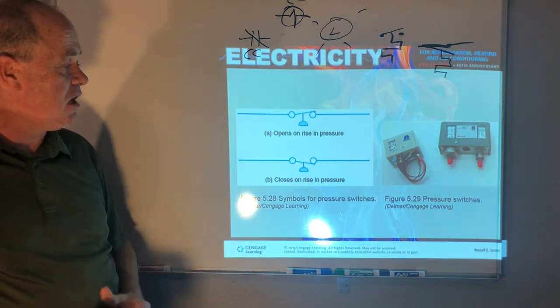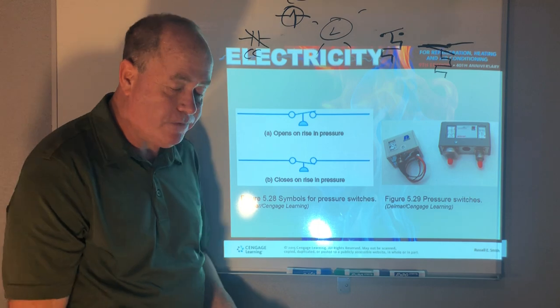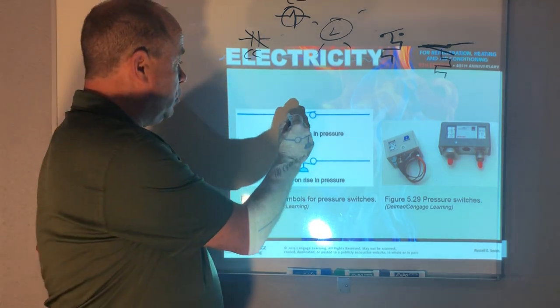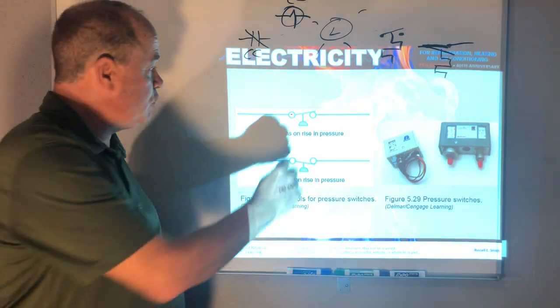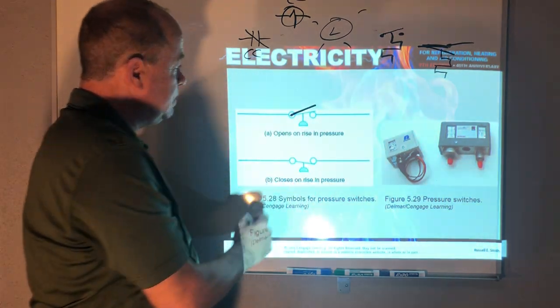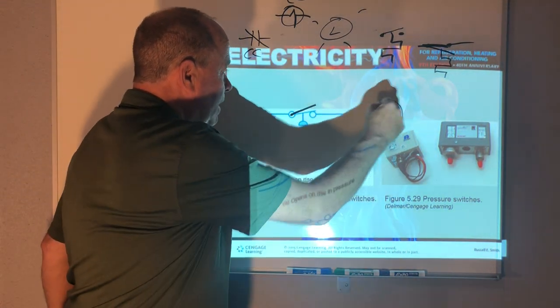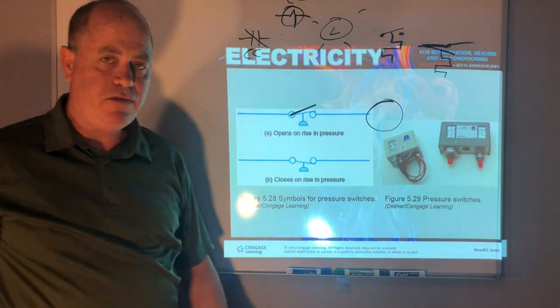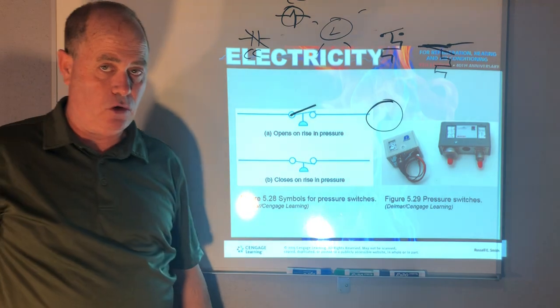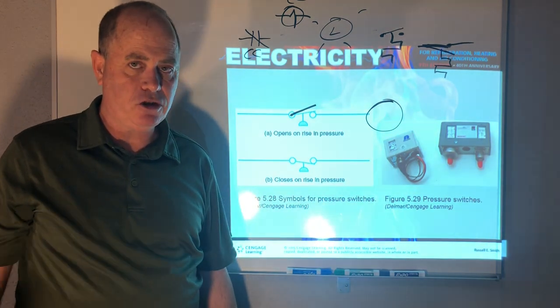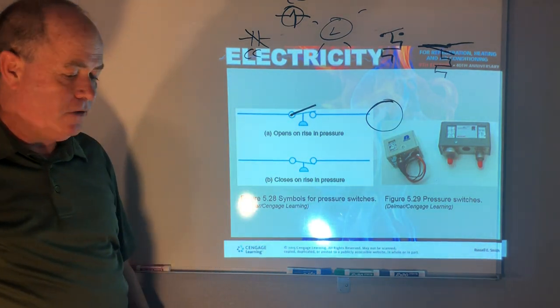And then this is your high pressure cutout. And this would open up if on a very hot day or you have a dirty condenser or the condenser fan motor goes bad and the pressure rises, it pops open and kills power that could feed the compressor or a contactor coil that then controls the compressor with a set of contacts.